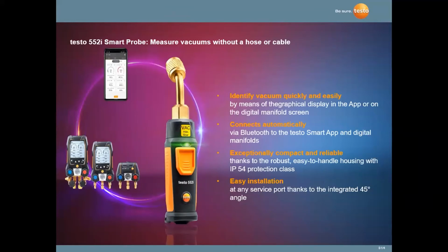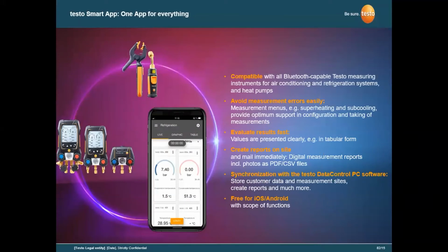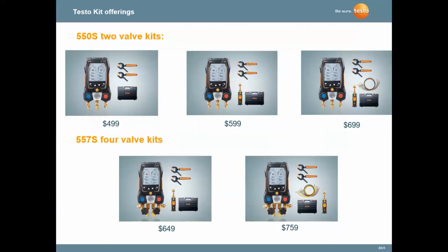There's less chance of having leaks when you pull a vacuum through the instrument. It's a very reliable vacuum micron gauge. Again, you're going from the digital smart probes to the instruments and then to the free Testo app. So if you're using a 550 or 557 digital gauge with a display, you've got two displays, a remote display and the local display on the instrument, providing graphics on both the app as well as the instrument.